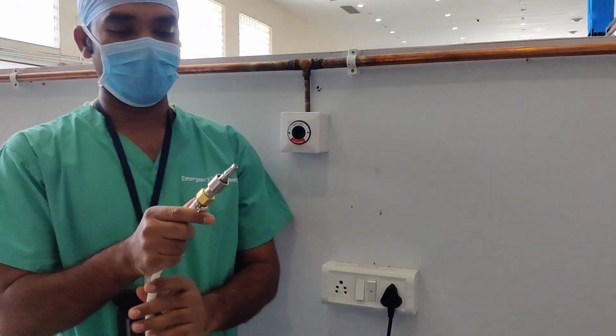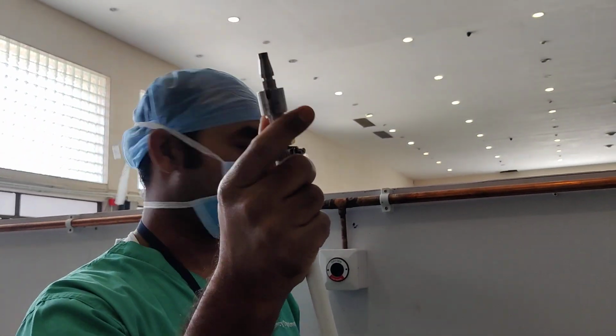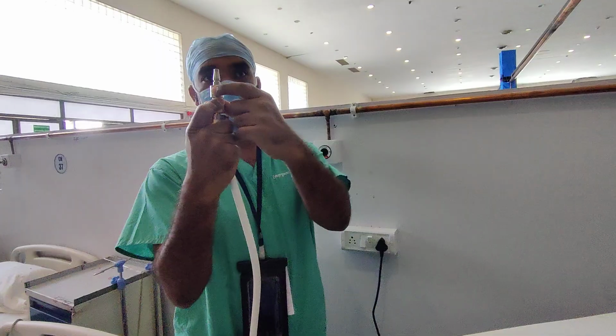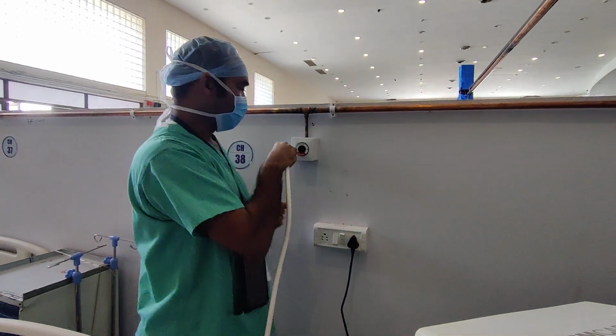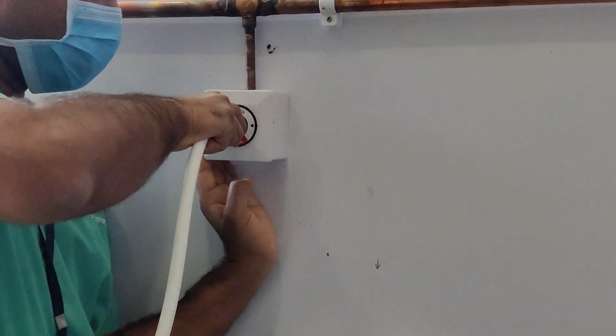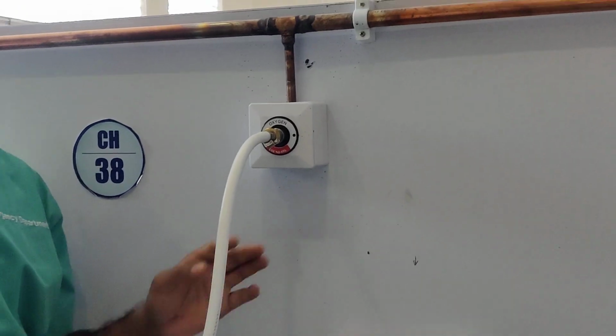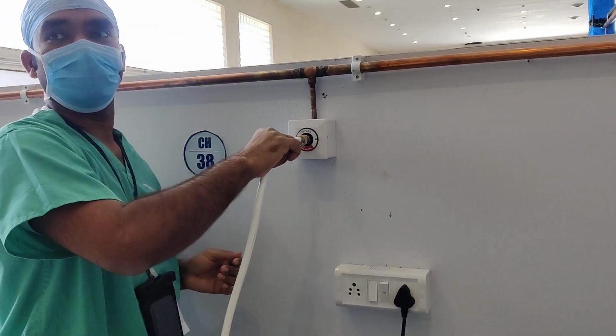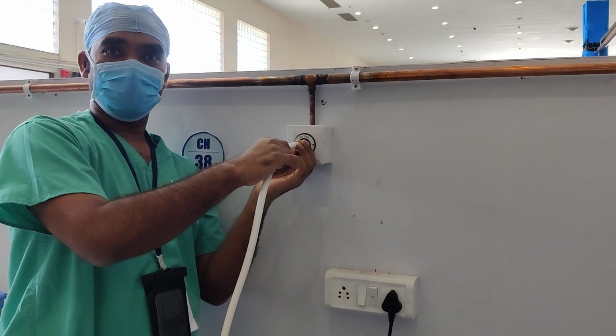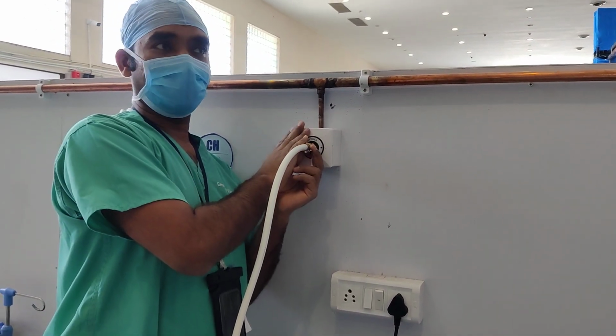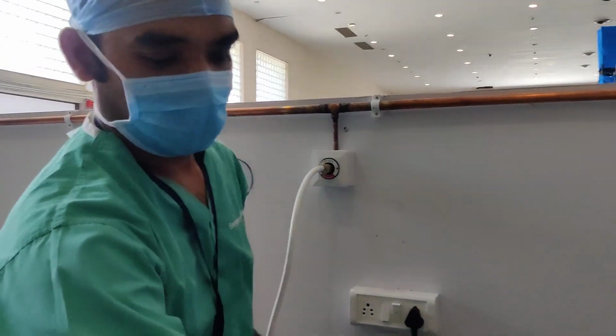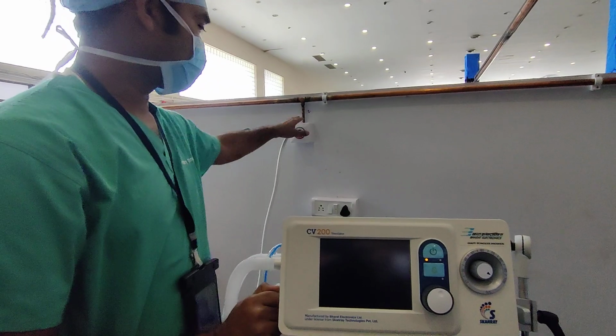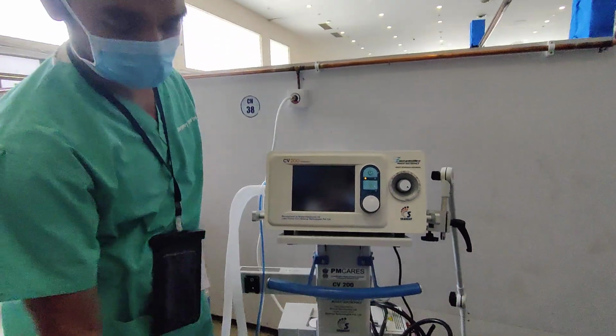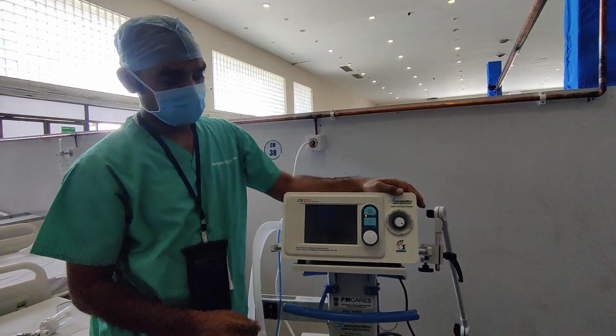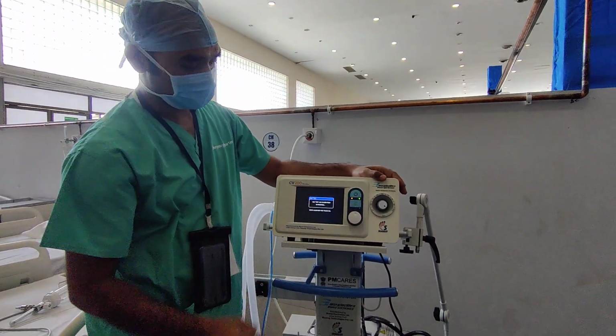Now let's go to the ventilator. The same way you have to connect the oxygen supply here as well. So this end will go on the upside. Okay, this end. So press it here and just keep it in and then just press it. How will you know that it's connected properly? Just try to pull it out gently. It won't come out. To take it out, you need to press this bit. Easy, everybody? You need to do this routinely, so you should know this by heart. So oxygen is connected, power supply connected, stabilizer is on, compressor is on. Now the ventilator. There is a switch on button here. So when you press the button, the machine will switch on.